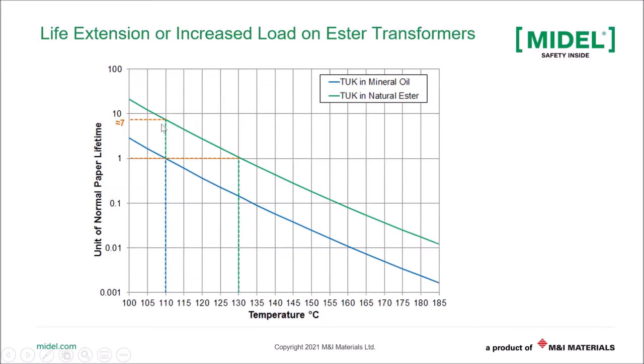Now, if the same cellulose material is used in an ester liquid, you can expect to have 7 times the life of the transformer, so over 100 years for the insulation system. On the other hand, if you increase the temperature to 130 degrees C, so 20 degrees C, you can get the same one unit life.